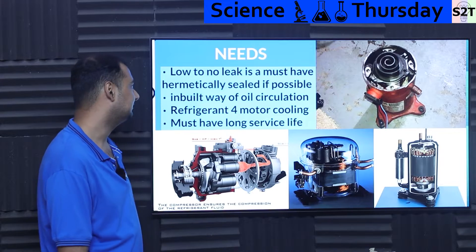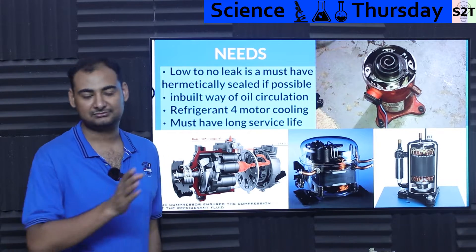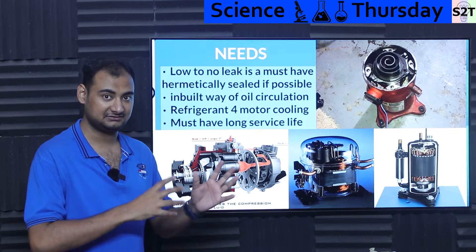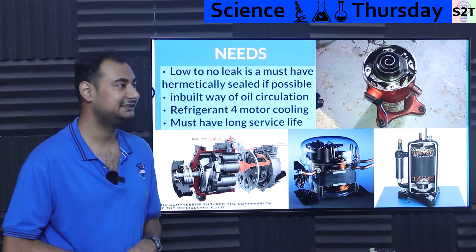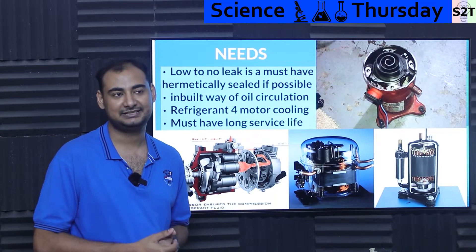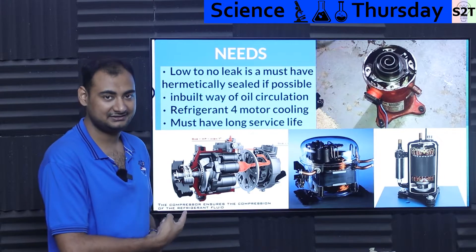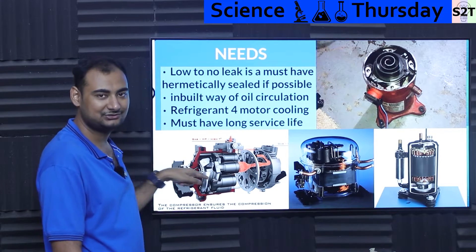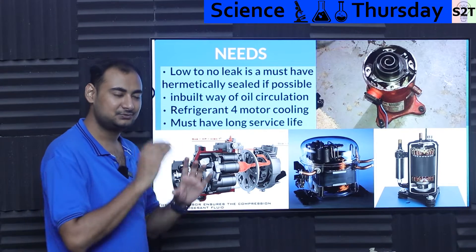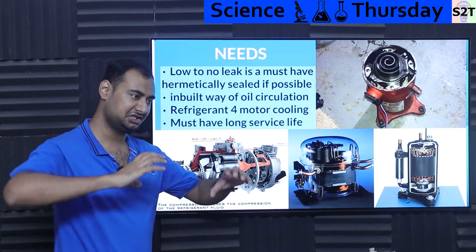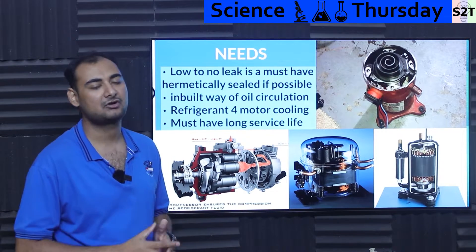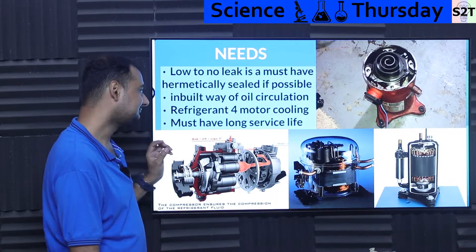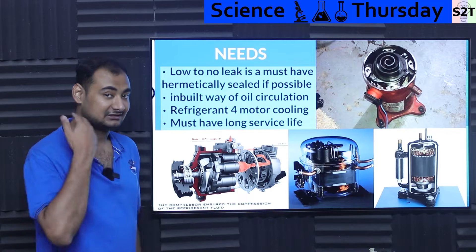What are the requirements of the compressor itself? It must not leak. During the era of transition from CFC to HFC, we realized very early that the refrigeration sector was leaking like crazy — and that's not acceptable. The worst example of a leaking AC system is your car system. It leaks so badly because it's not hermetically sealed — you have a shaft going through the pressurized system. Back in the 1950s, that's how it was done, but a spinning shaft is very hard to seal. Make the glands too tight and it won't leak but will need lots of horsepower and become loose after a few minutes.